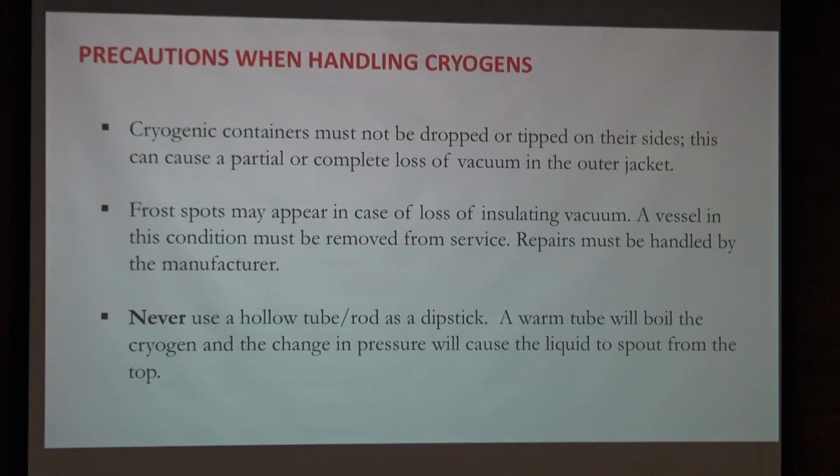That's what the general knowledge is. Don't use a hollow tube or rod as a dipstick to put into the dewar to check how much cryogen is still in there. That will evaporate quite a lot of cold liquid and can create either escaping gas or an increase in dewar pressure.